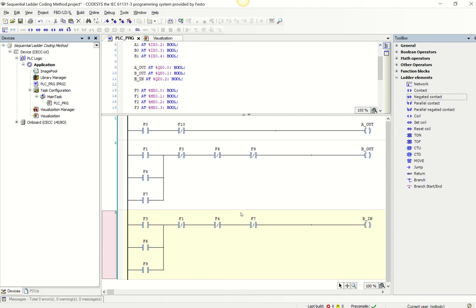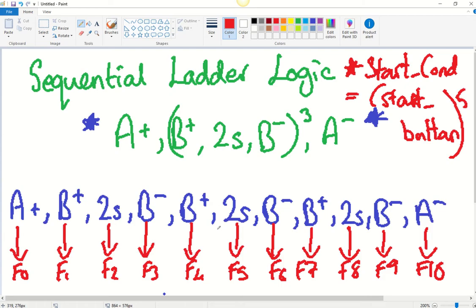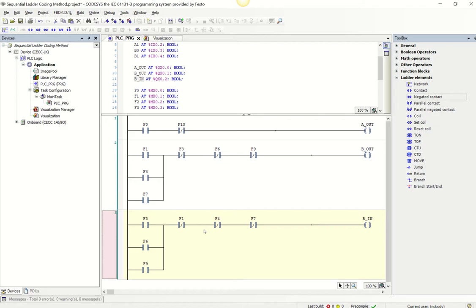That's the first element — defining at what steps we want our outputs to turn on. The next element is signifying how we get from one step to another, and what inputs trigger the steps. Here we're only using markers to trigger the outputs — no physical inputs appear in those output rungs. Below this, we'll use physical inputs to trigger when the steps happen.